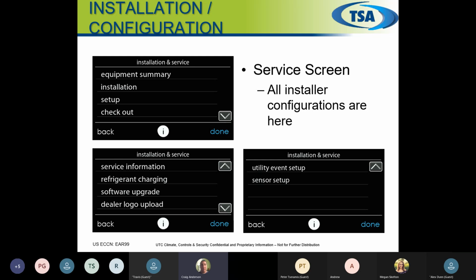Now, the background of the thermostat is just something where you can go in and you can tweak a couple things. So equipment summary, you can go in there and see what's going on. We can go into installation, setup, check everything out. Service information, refrigerant charging system. This will help you charge the refrigerant in an outdoor unit. It's going to tell you some subcooling and stuff like that.